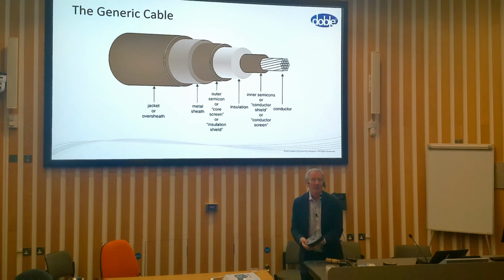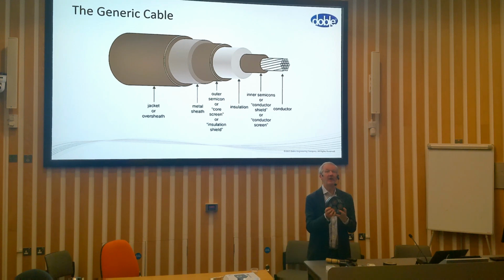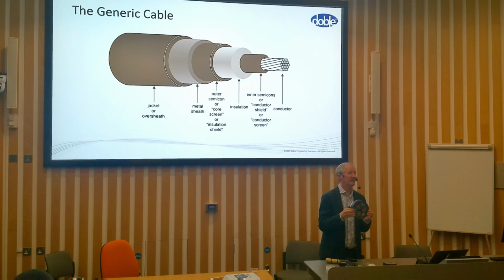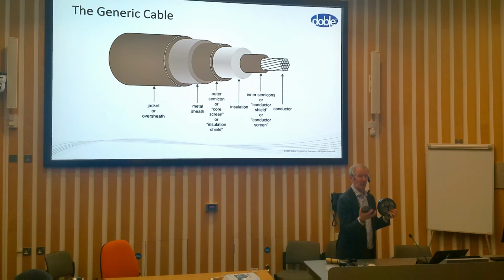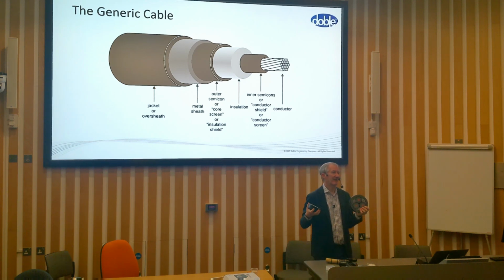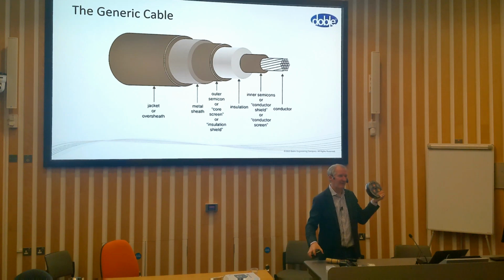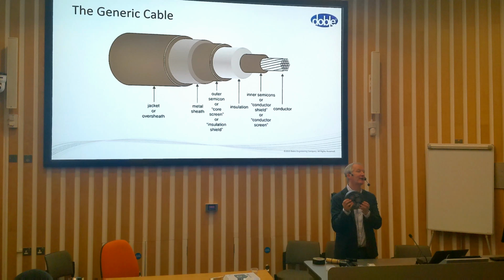If it's a subsea cable, I'm not going to pass this around, this is only a 66 kV cable. If you imagine scaling that up, this one is I think 132, so a little bit bigger, and you'd have three of these in the bundle. If it's 400 kV, this gets very, very big. This has steel armor wire on the outside, because it's going to get put on the bottom of the ocean, and it has to protect against movement on the seabed, rocks, and people with anchors.